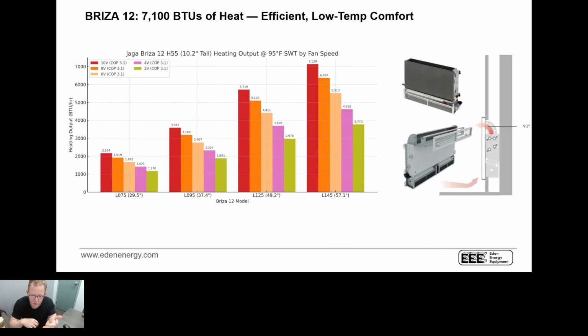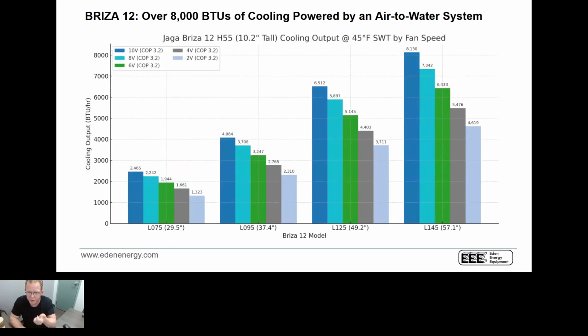other advantages for builders: no bulkheads, no taping, no drywalling, no painting. There's fire code regulations that help them here. There's zoning from an operative carbon standpoint. There are so many good things on this slide for a builder that have nothing to do with a contractor or an installer. But the key thing is this is a way to heat the home using 95-degree water and getting upwards of 7,100 BTUs per room if you needed that in a very compact and concealed footprint.